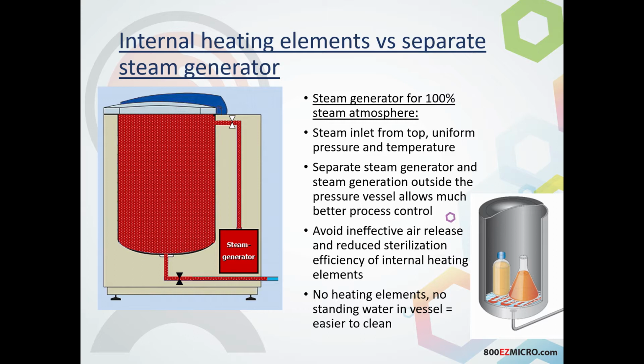air release, because the only way the air is going to get out of the autoclave is if it were at the top. But the air is heavier than the steam, so it sits at the bottom, and there's no way to get it out of the bottom because there's water sitting in the bottom. So it's impossible for us to be able to actually fill that full of steam. So the area where your bottles are sitting inside of that autoclave right now are sitting in a nice little air pocket with steam above it and heaters below it. But there's actually no steam penetration to the load at that point.